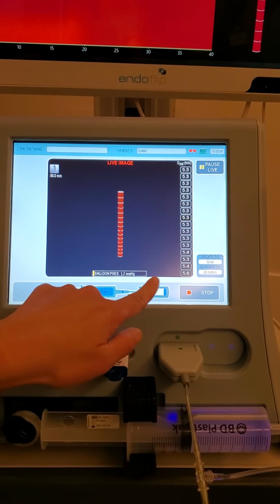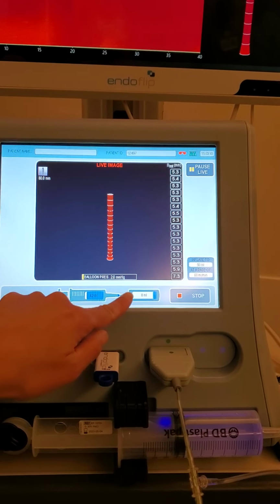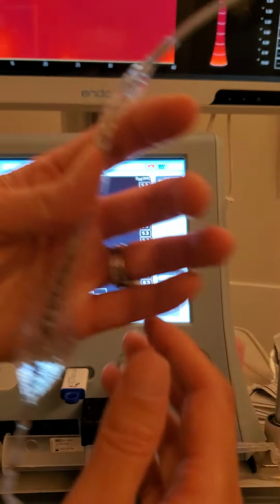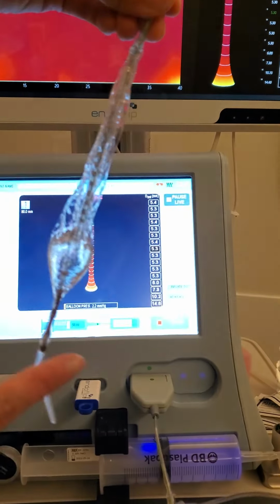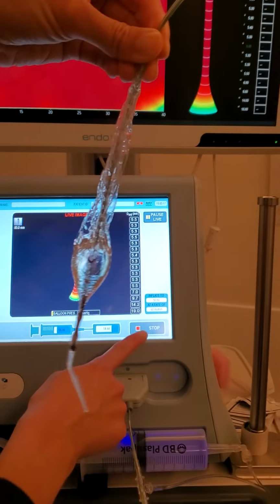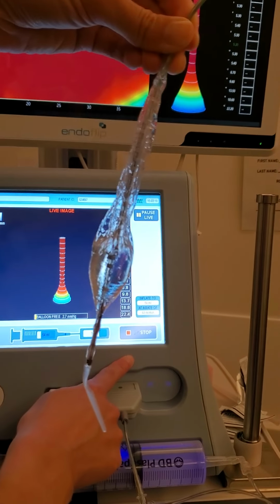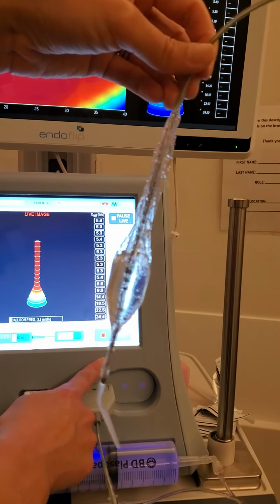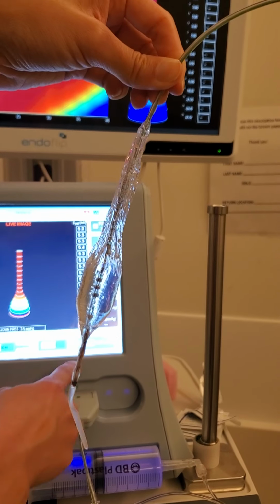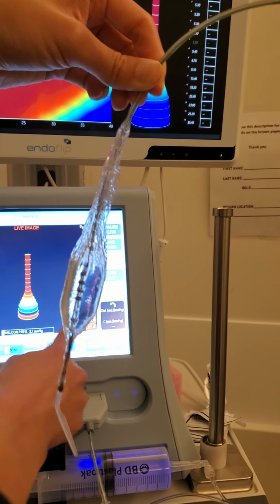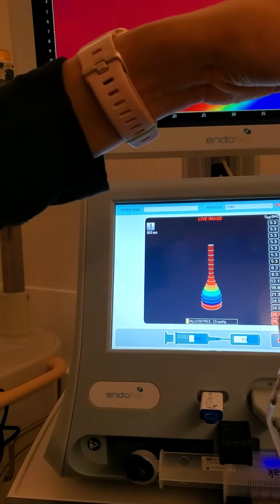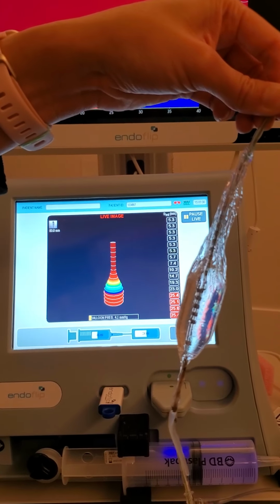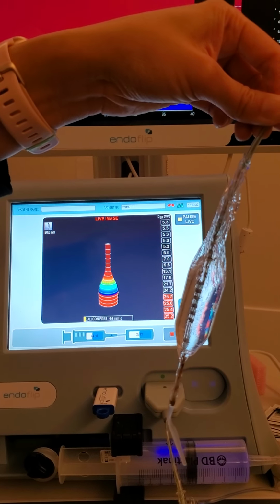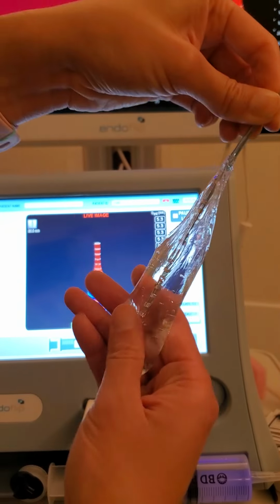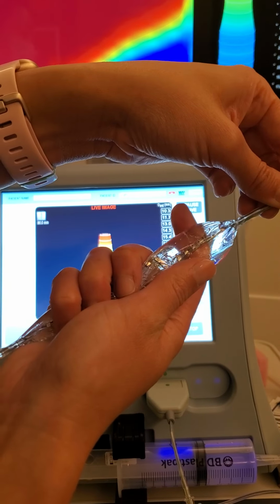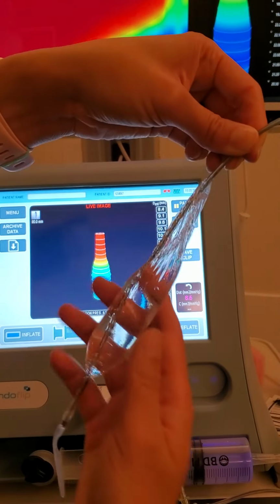You're gonna watch this box right here, this rectangle. It is the amount of liquid inside of the balloon. So what it's doing is injecting liquid into the balloon, and you're gonna stop it when it gets to a certain volume. The doctor should always tell you what volume they want, but usually they have you inflate to 20, stop, and then inflate to 30. So you see the balloon is growing. Yeah. If this was inside of a lumen, it would be. So we would stop at 30.